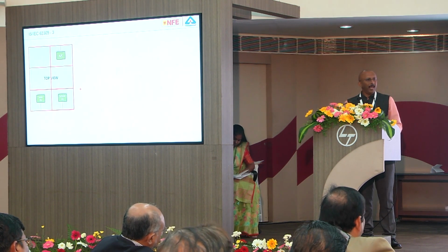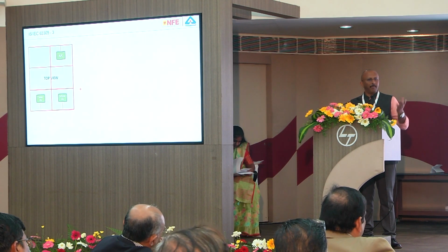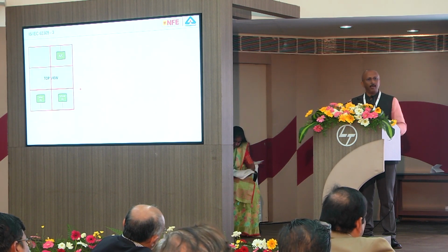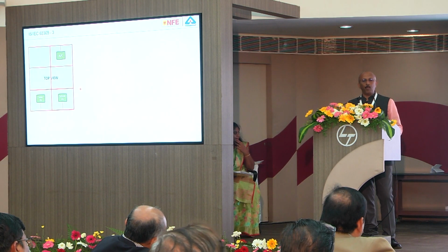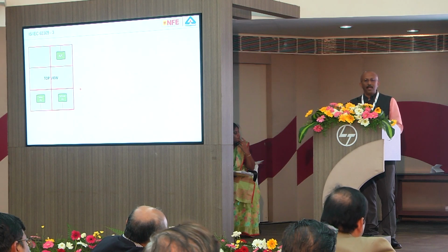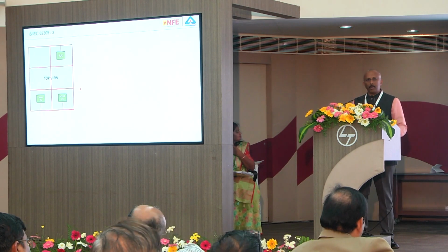Then all the metallic items at the roof must be bonded to the air termination grid. Let's say you have a chiller, maybe some ladder, or an antenna, or some pipe. All these metallic objects must be connected or bonded to the lightning protection air termination grid. I just put an example. There are 2 techniques here. One is you isolate the lightning protection. The second technique is you bond. Isolation is sometimes applied in certain places, bonding is applied in certain places. Let us think that I am going with the principle of bonding. This means all metallic parts at the roof must be bonded to the air termination system.